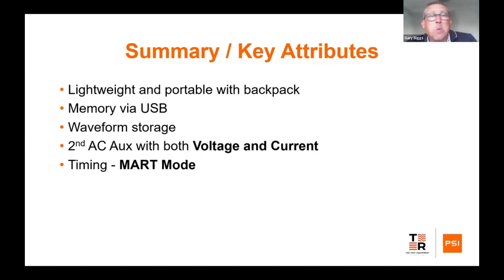So, the summary: what are the key attributes of this particular tester? It's lightweight, it's portable, and it's backpackable. You can literally wear it as a rucksack. It's got memory via the USB, and that's something you don't see on many mechanical relay test sets. We have the ability to store waveforms. Any engineer that's ever had the hassle of going onto site and getting strange results knows that 9 times out of 10, if your relay's giving you weird results, it's because the waveform isn't correct, but you've got no way of telling that unless you happen to take an oscilloscope with you.